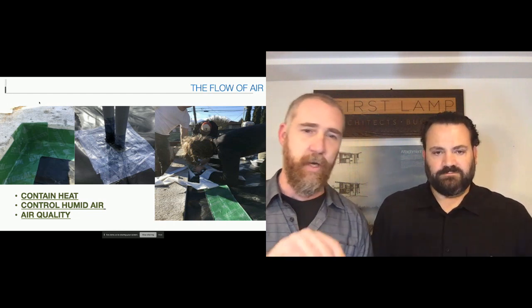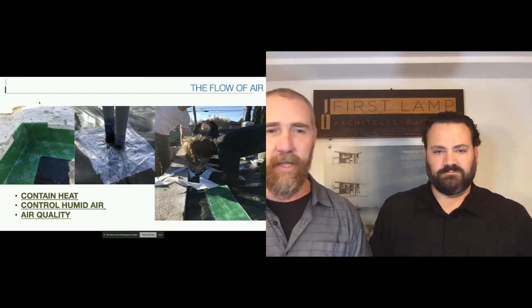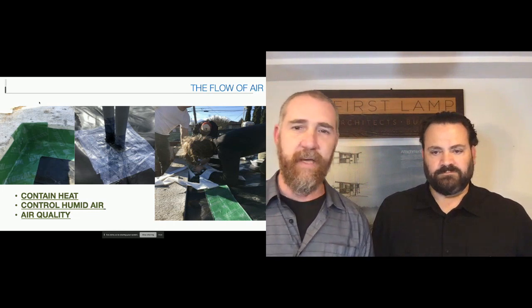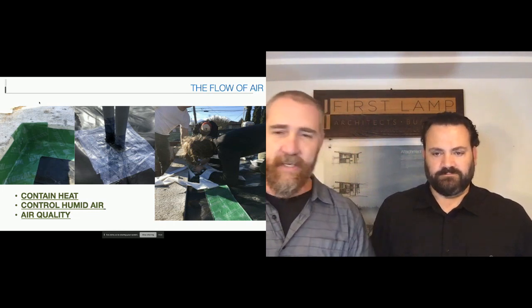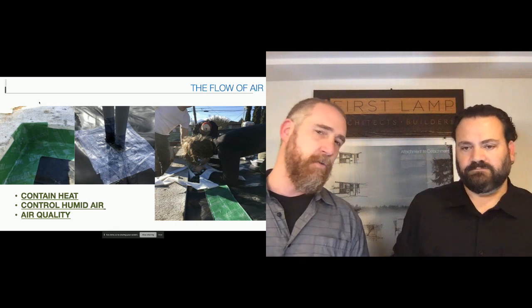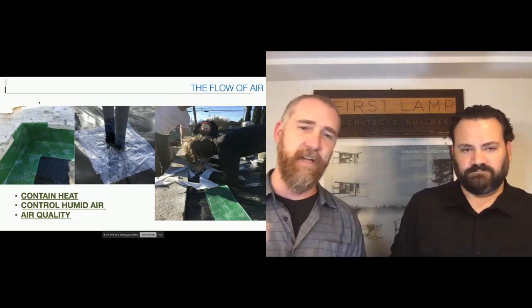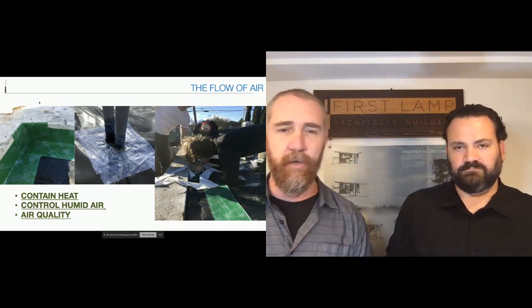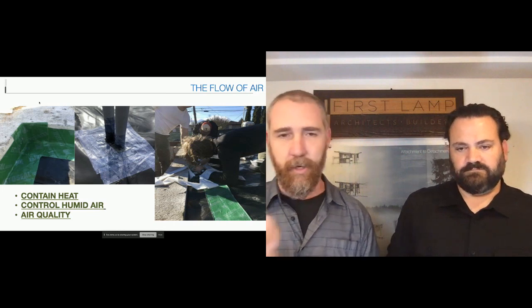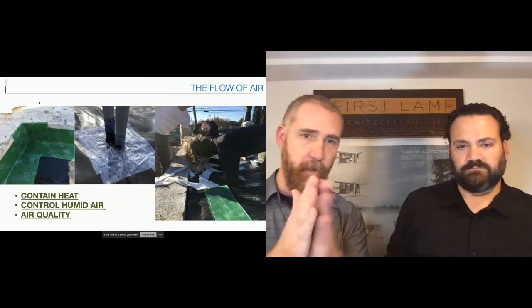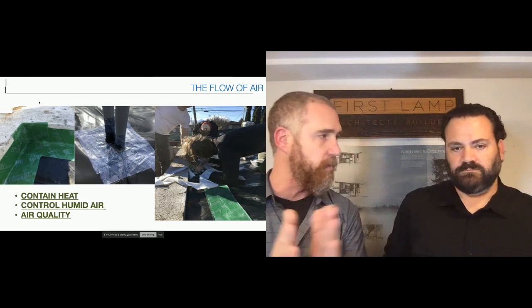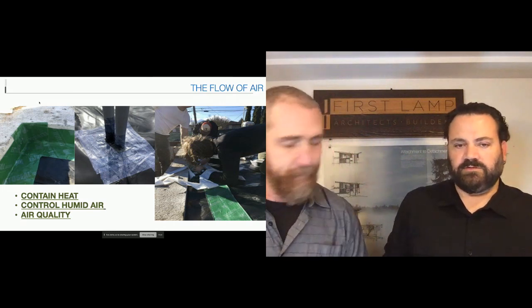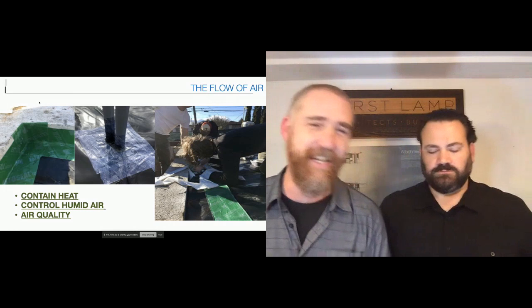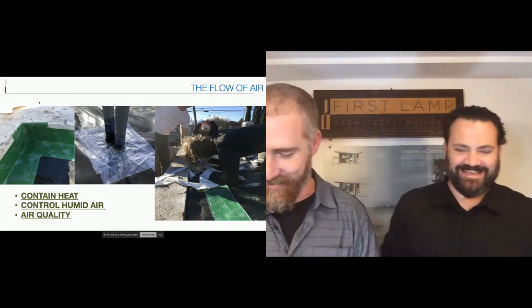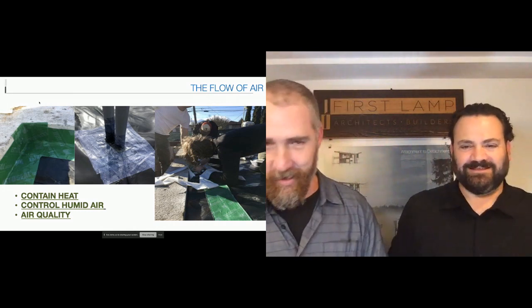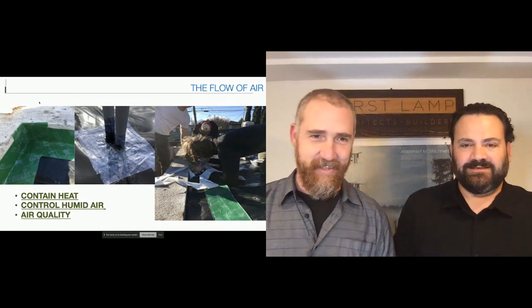Conduit as it comes up through the slab for the kitchen island, slab edge, all of that stuff - tapes are fantastic, expanding foam is not so much. Tapes stay flexible as the building moves over the years. Foam becomes rigid and can detach from the things you're trying to close the gap around. Don't even start with me on caulk - just get out of here with the caulk. Tapes for the win.